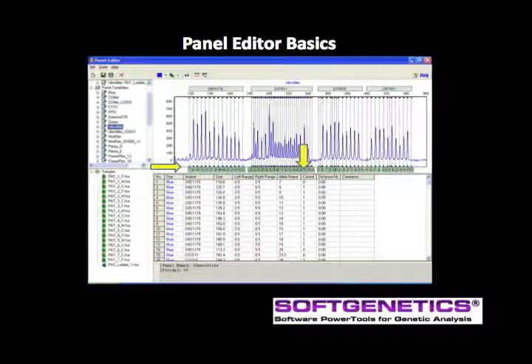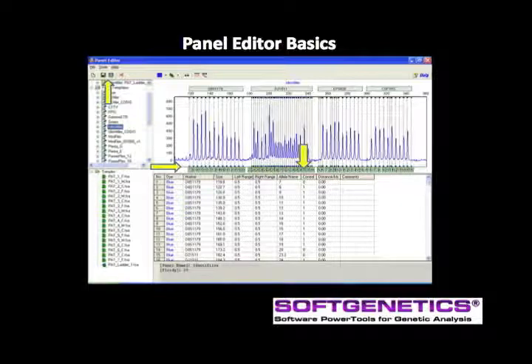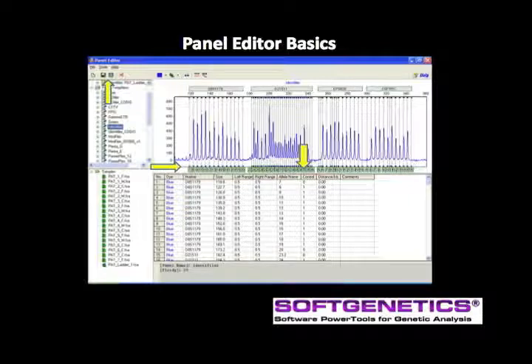Major alleles are denoted by a one in the control column. The first time that a different genetic analyzer is processed, the lab manager should confirm the panels are aligned and saved with signal information to calibrate the panel to the instrument. Details of panel calibration are found in the user manual.